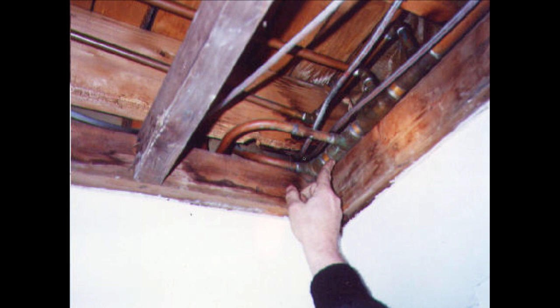So they didn't have any heat up there in the bathroom. So Al and I are looking at this and we're saying, imagine you're water. If you were water and you're flowing down this line, would you go from here to here, even though there's a Diverter tee in there, or would you choose to go up this pipe all the way up to the second floor and then all the way back down to this tee? What would you do if you were the water? And the answer was pretty clear, we'd stay in the pipe. So that was a problem.